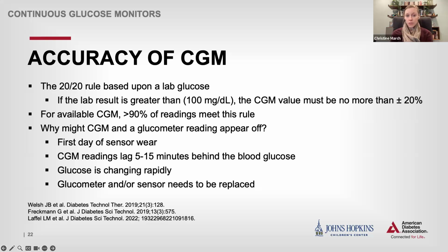Now, if you were to have a fingerstick reading at the time of a sensor reading, you may notice at times they look off, and there could be different reasons for this. The first is that it may be the first day of sensor wear. They all have a warm-up period, and there may be some less accurate readings that first day. The other thing to keep in mind, if you recall, is that the CGM reading will lag 5 to 15 minutes behind the blood glucose, and so that could lead to a small discrepancy. But if the glucose is changing rapidly, that could lead to a much greater discrepancy between the two. The last potential is that the glucometer or the sensor may need to be replaced. Certainly, not every device is perfect, and sometimes they do fail. And this is actually a reason why we usually test both the sensor and the patient's glucometer against a calibrated measure at their clinic appointments.